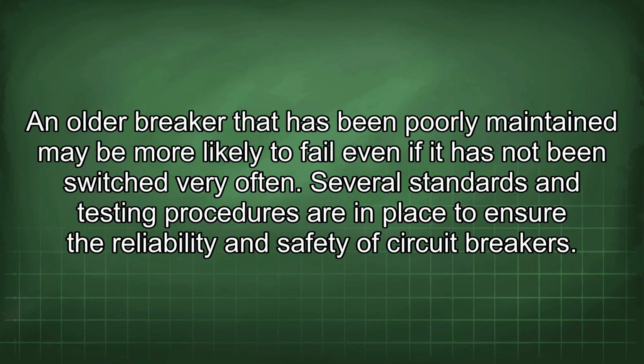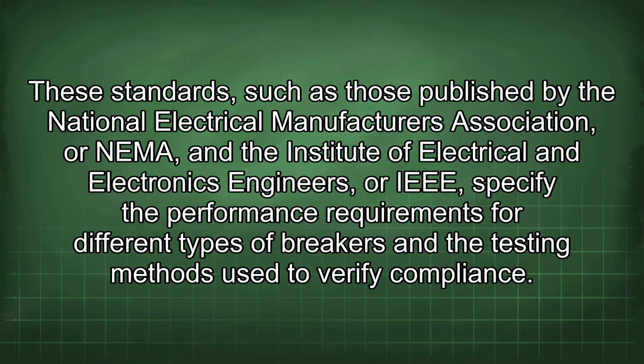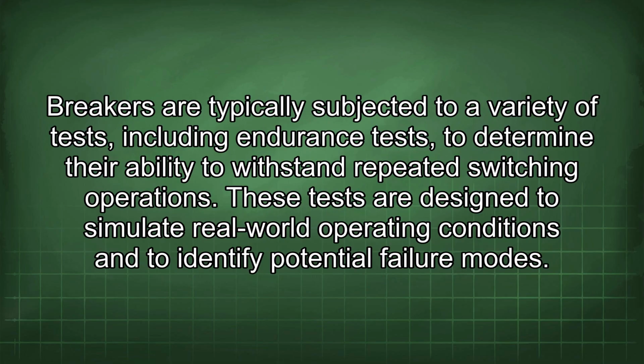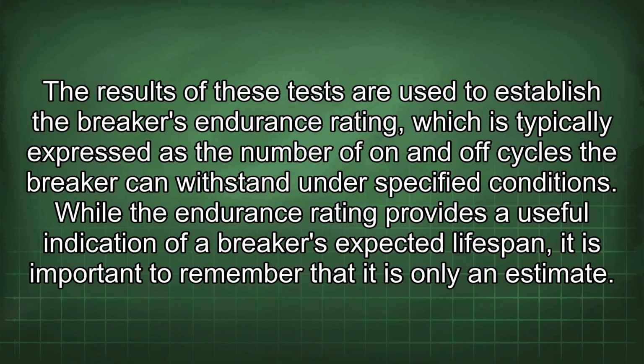Several standards and testing procedures are in place to ensure the reliability and safety of circuit breakers. These standards, such as those published by the National Electrical Manufacturers Association, or NEMA, and the Institute of Electrical and Electronics Engineers, or IEEE, specify the performance requirements for different types of breakers and the testing methods used to verify compliance. Breakers are typically subjected to a variety of tests, including endurance tests, to determine their ability to withstand repeated switching operations. These tests are designed to simulate real-world operating conditions and to identify potential failure modes. The results of these tests are used to establish the breaker's endurance rating, which is typically expressed as the number of on and off cycles the breaker can withstand under specified conditions.